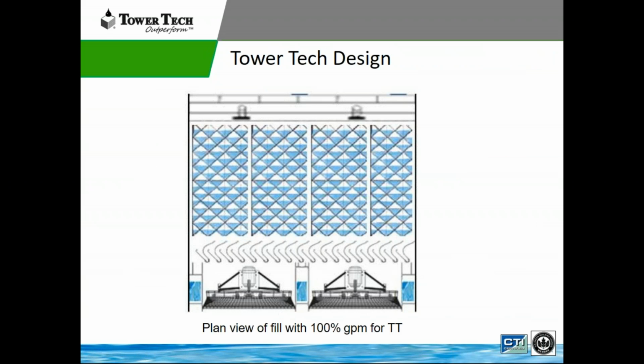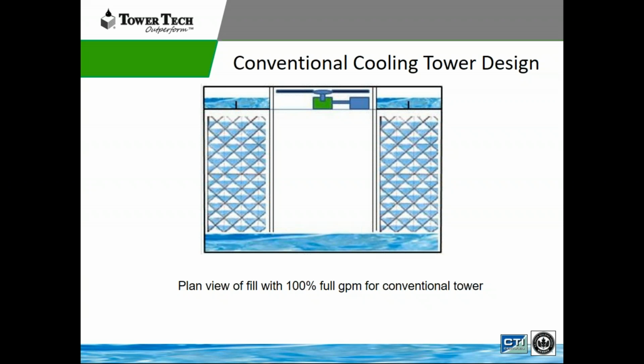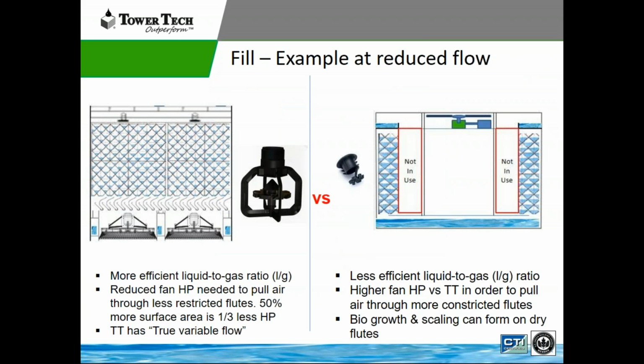Okay, so we're going to look at the TowerTech design. Here's a planned view of fill with 100% GPM for a TowerTech system, and you'll notice that the fill is all filled. This is 100% flow. When we look at a traditional system, conventional tower system with the weirs, again, the fill is all filled, 100% full GPM, design day, conventional cooling tower. So in this case, we're very similar from an efficiency standpoint.